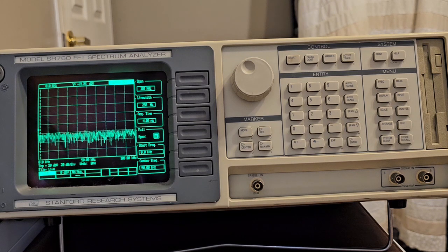The soft keys have a menu-driven interface. The 6 soft keys to the right of the video display have different functions depending upon the information displayed in the menu boxes at the right of the video display. In general, the soft keys have 2 uses. The first is to toggle a feature on and off or choose between settings. The second is to highlight a parameter which is then changed using the knob or numeric keypad. In both cases, the soft keys affect the parameter which is displayed adjacent to it.